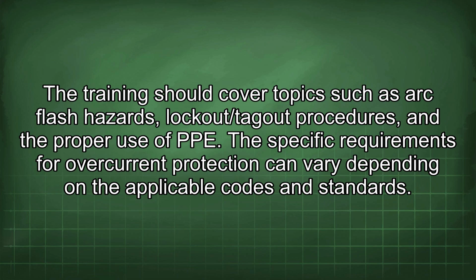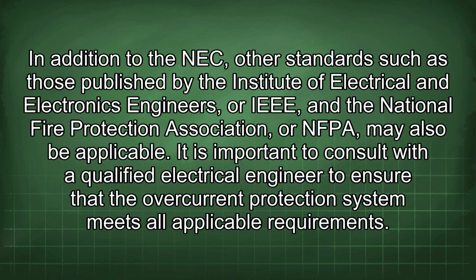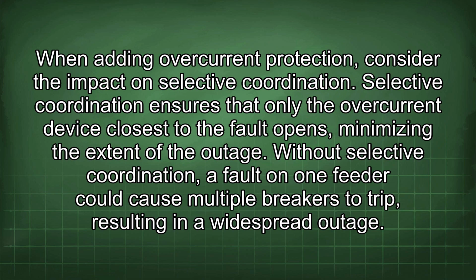The specific requirements for overcurrent protection can vary depending on the applicable codes and standards. In addition to the NEC, other standards such as those published by the Institute of Electrical and Electronics Engineers, or IEEE, and the National Fire Protection Association, or NFPA, may also be applicable. It is important to consult with a qualified electrical engineer to ensure that the overcurrent protection system meets all applicable requirements. When adding overcurrent protection, consider the impact on selective coordination. Selective coordination ensures that only the overcurrent device closest to the fault opens, minimizing the extent of the outage. Without selective coordination, a fault on one feeder could cause multiple breakers to trip, resulting in a widespread outage.